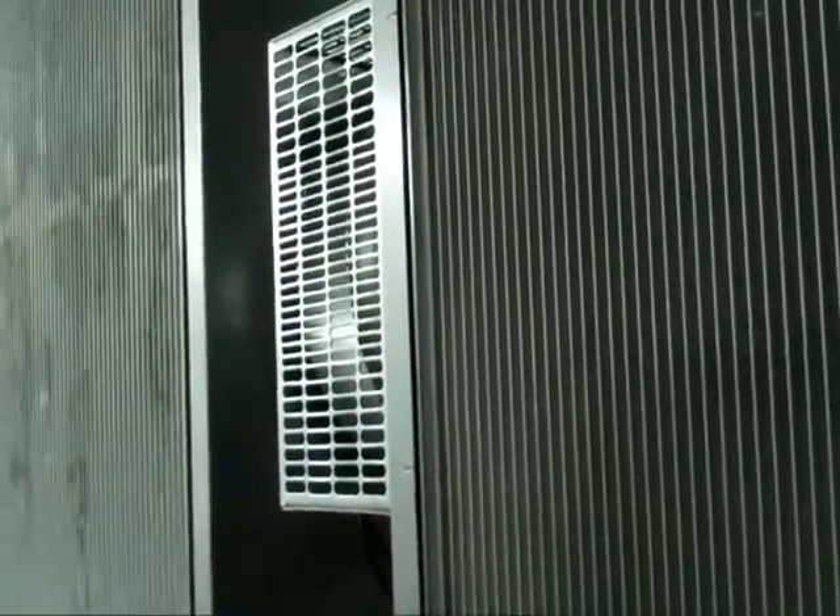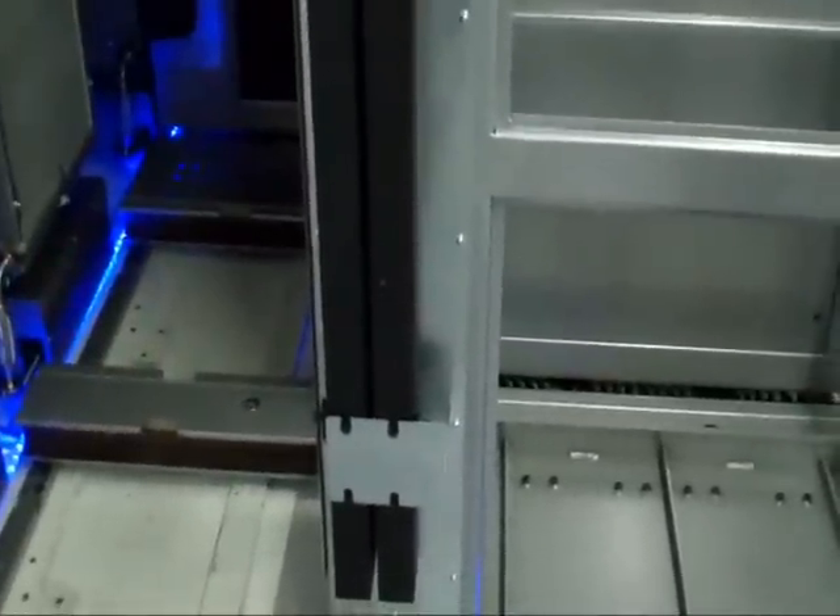This essentially becomes the hot air plenum here. Air is pulled out the back of the cabinets — the servers are right here — pulled into the condenser, pushed out with the fans, and recirculates back through the front of the unit, pulled back in through the front with the servers. These racks are mounted on sleds so it's easy to slide in and out as a single operator even if they're fully loaded. Normally the rack would be installed up against the cooling system in the back.